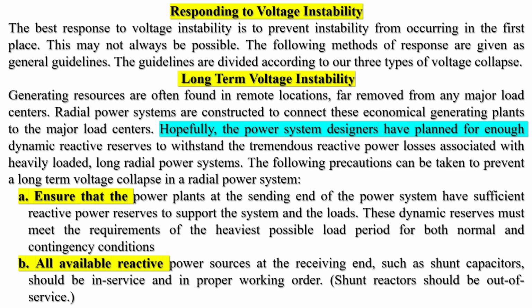Ensure that the power plants at the sending end of the power system have sufficient reactive power reserves to support the system and the loads. These dynamic reserves must meet the requirements of the heaviest possible load period for both normal and contingency conditions. All available reactive power sources at the receiving end, such as shunt capacitors, should be in service and in proper working order. Shunt reactors should be out of service.